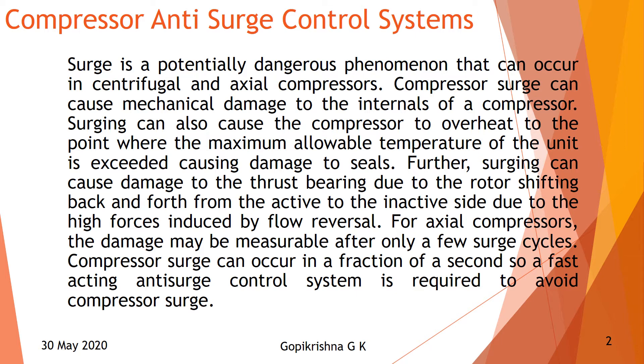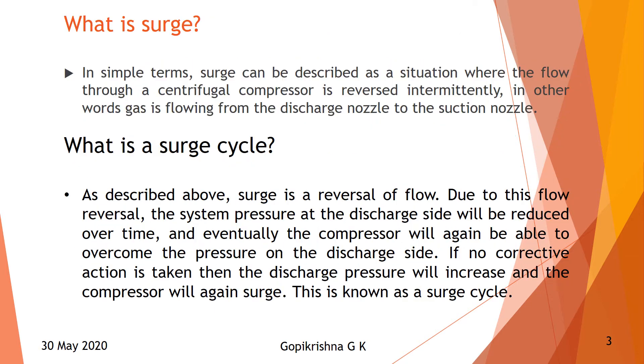Compressor surge can occur in a fraction of a second, so a fast anti-surge control system is required to avoid compressor surge. Simply, in simple terms, surge can be described as a situation where the flow through the centrifugal compressor is reversed intermittently — in other words, gas is flowing through the discharge nozzle back to the suction nozzle. This is called a surge cycle. The surge is a reverse flow — once the discharge nozzle opens and flow reverses.